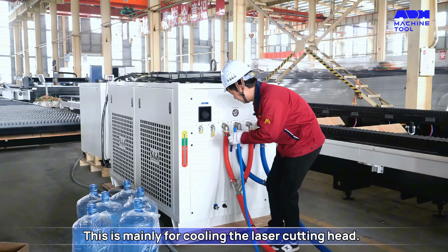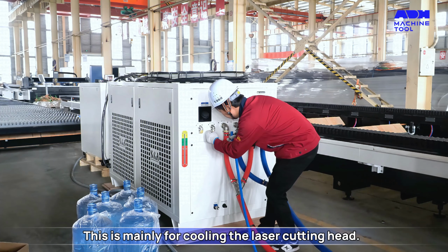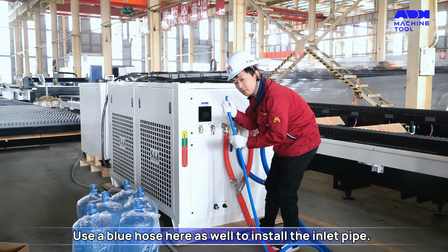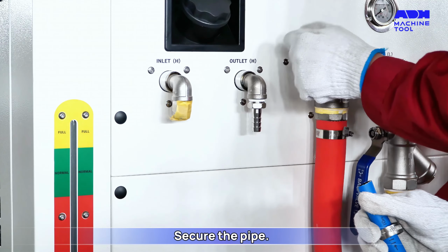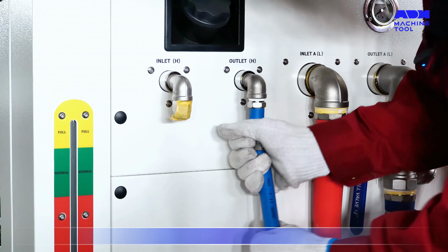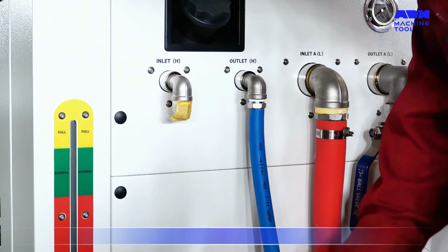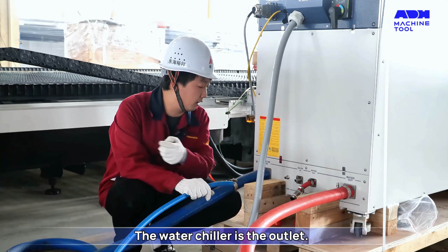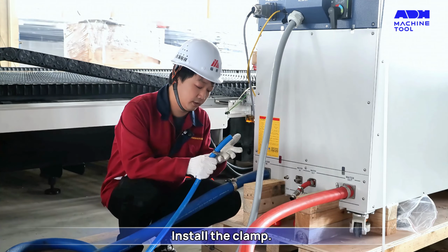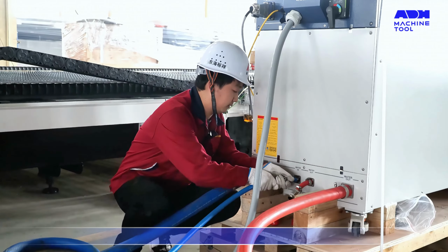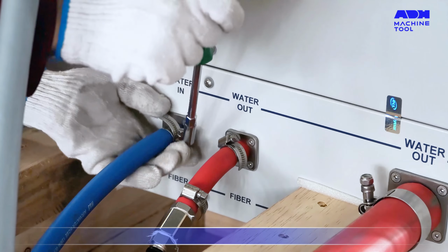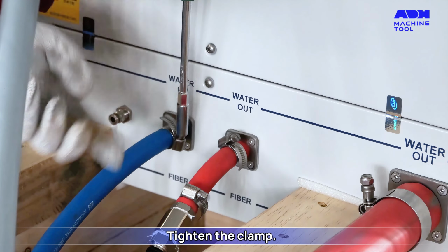This is mainly for cooling the laser cutting head. Use a blue hose here as well to install the inlet pipe. Secure the pipe. Install the clamp. The water chiller is the outlet, the laser is the inlet. Install the clamp. Tighten the clamp.